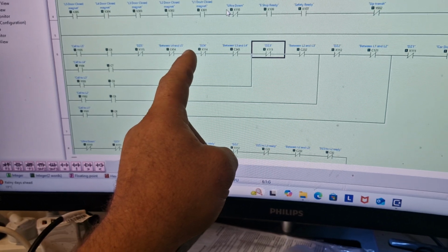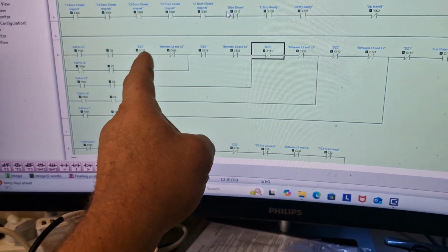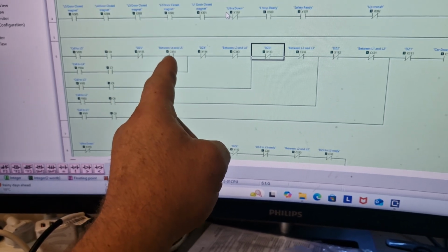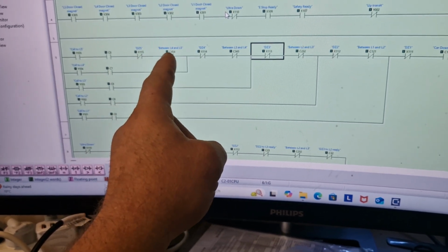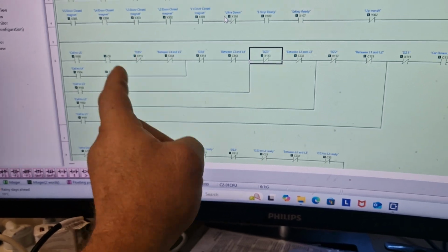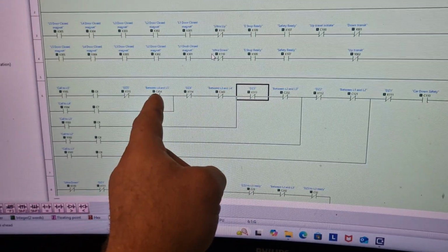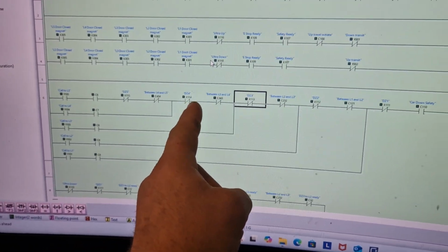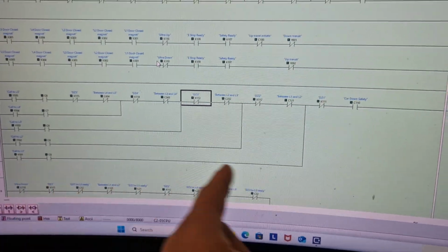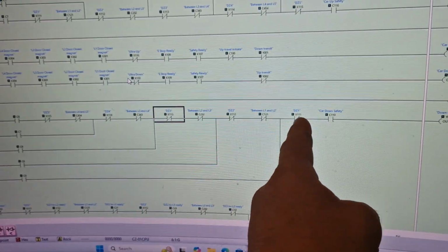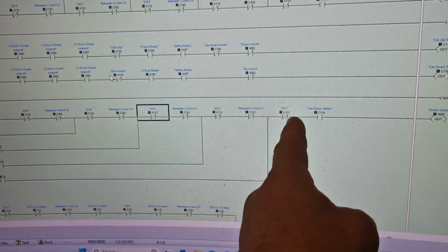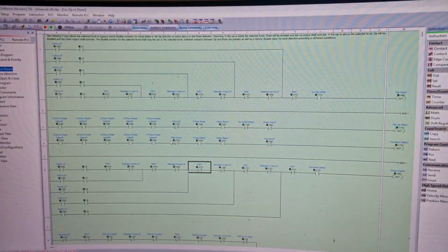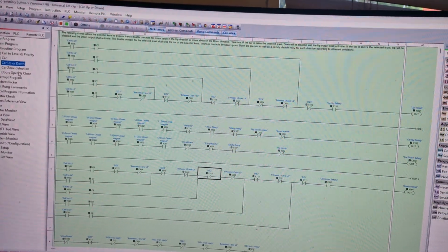and it happens to be above level 4 here, which is level 5 sensor and the transit between, which I've managed to work out in other programming. There we go. It will be open here, so the down contactor will be on, and it won't stop until it gets to level 4, and then this will open, thus opening that. Likewise, level 1, it'll continue traveling down all the way until it hits the level 1 proximity sensor, and then turn off. So as you can see, that's an example of an array to make a complicated situation very simple.